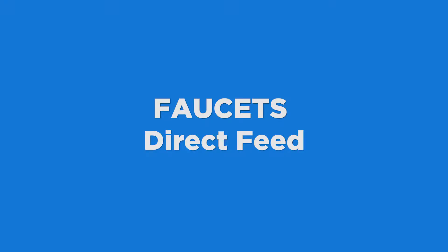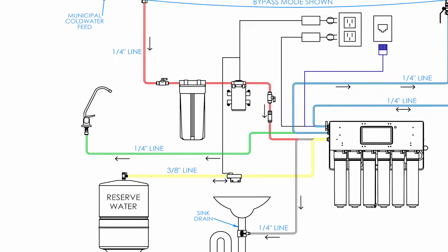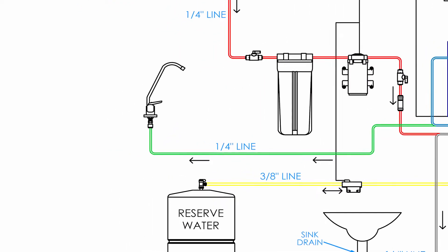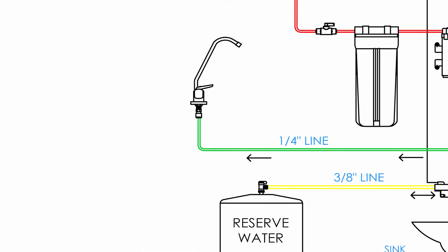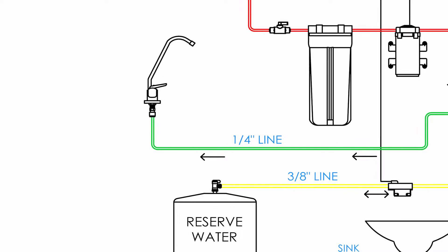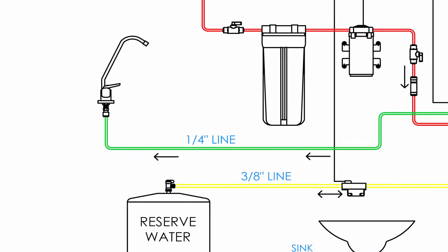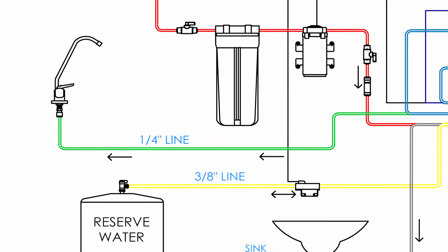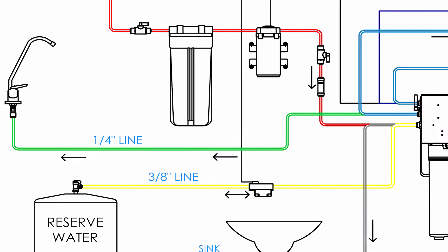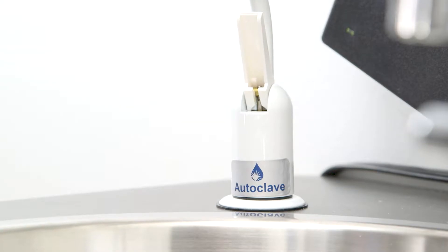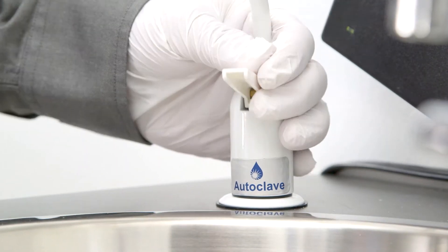Faucets. Direct feed. The direct feed configuration comes with only a white autoclave faucet. Dental water is plumbed directly to the handpiece from the system. The faucet can be mounted on a countertop or on a wall using an optional remote mounting bracket. For the purposes of this demonstration, we'll go over countertop mounting.